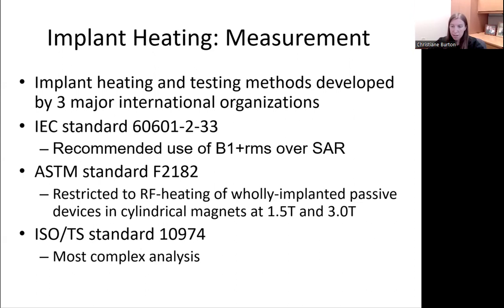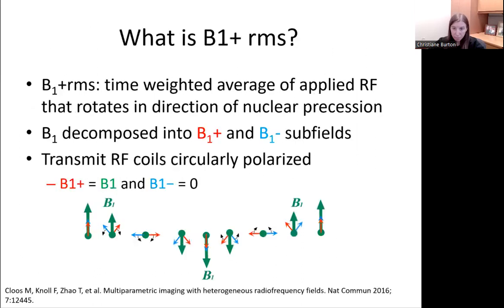The ASTM standard F2182 is restricted to RF heating of fully implanted passive devices in cylindrical magnets at 1.5T and 3T. I'll show an image of this method in a future slide. The ISO/TS is the most comprehensive approach to implant heating issues. A 4-tiered approach is taken, each level progressively resulting in less restrictive conditions for imaging for the implant, but requiring a more complex analysis. I'll go into each one briefly, starting with the IEC's method.